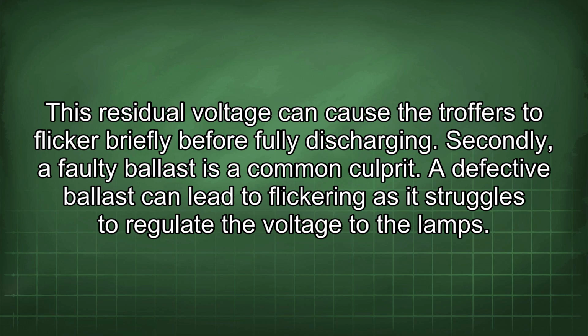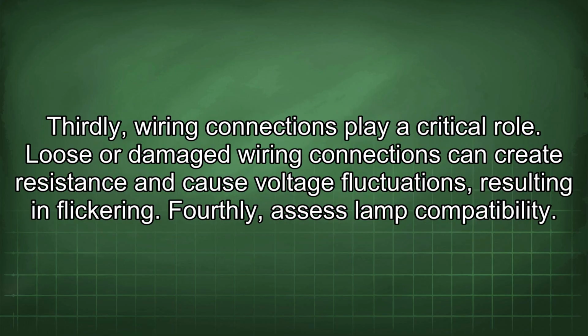Secondly, a faulty ballast is a common culprit. A defective ballast can lead to flickering as it struggles to regulate the voltage to the lamps. Thirdly, wiring connections play a critical role. Loose or damaged wiring connections can create resistance and cause voltage fluctuations, resulting in flickering.